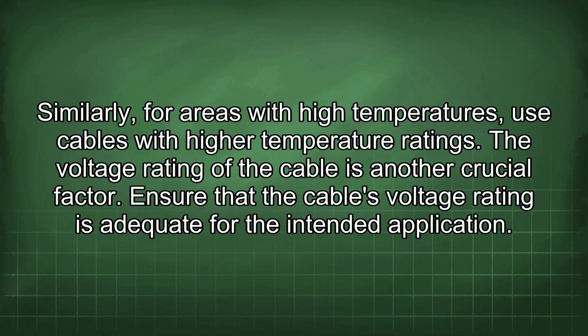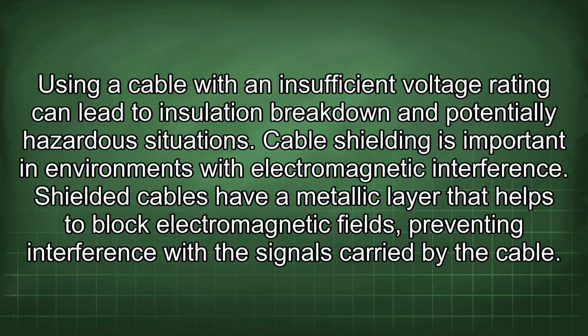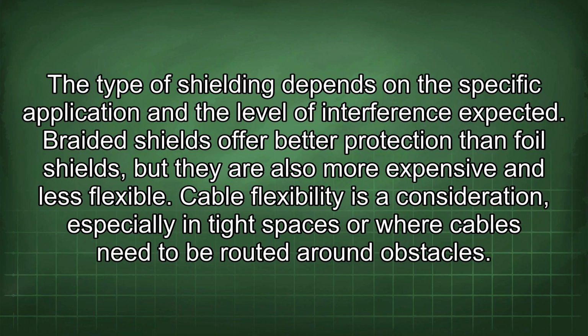The voltage rating of the cable is another crucial factor. Ensure that the cable's voltage rating is adequate for the intended application. Using a cable with an insufficient voltage rating can lead to insulation breakdown and potentially hazardous situations. Cable shielding is important in environments with electromagnetic interference. Shielded cables have a metallic layer that helps to block electromagnetic fields, preventing interference with the signals carried by the cable. The type of shielding depends on the specific application and the level of interference expected. Braided shields offer better protection than foil shields, but they are also more expensive and less flexible.